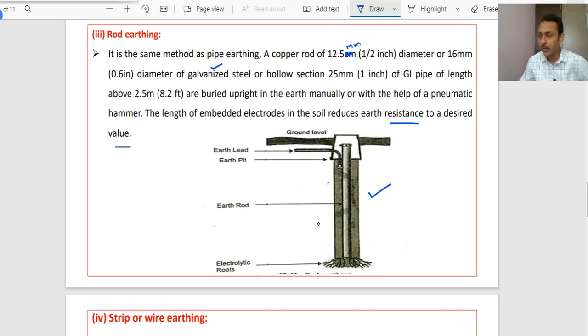Now the length of the electrode embedded in the soil is going to reduce the earth resistance to the desired value. Whatever arrangements we are doing, the purpose is to offer as low a resistance as possible, because once the resistance is as low as possible, more leakage current can pass through the earthing system. For that sake, every time you are making use of charcoal, salt and a wet watering system arrangement. And the materials you are using are copper rod, galvanized steel or galvanized iron pipes. These are the materials we are using in the earthing system, right?